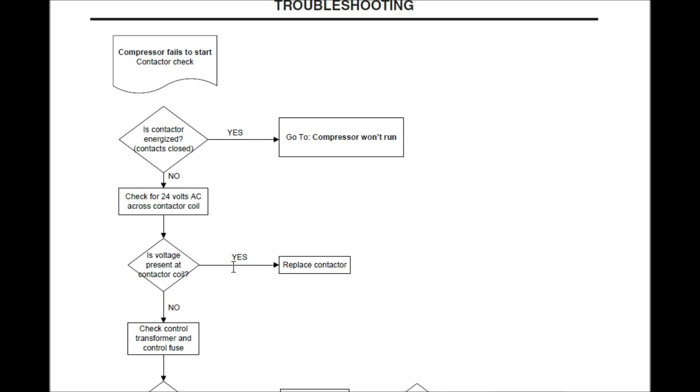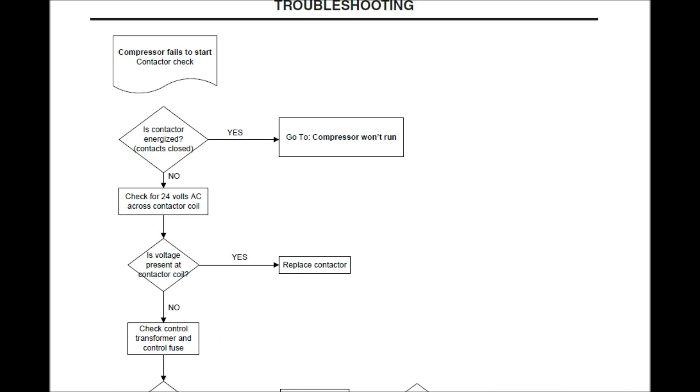Is voltage present at the contactor coil? If yes, we need to replace the contactor coil. If no, we need to check the control transformer and control fuse.